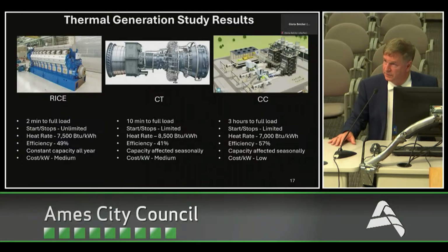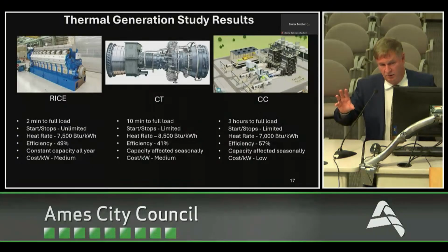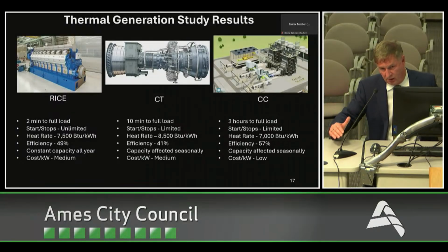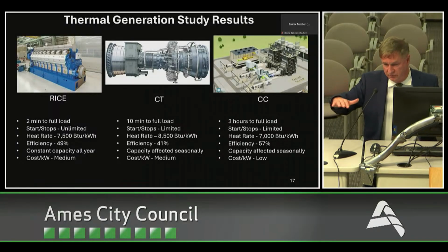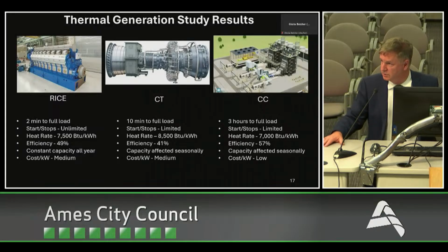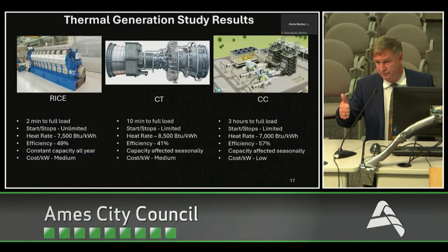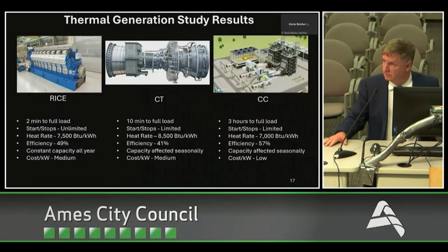It's not the starting and stopping that hurts a unit like that. It's the thermal cycling, when you let it cool down and then let it start up again. So if you keep it at a fairly constant temperature, what you really need is probably an upgraded starter and batteries to start it up.